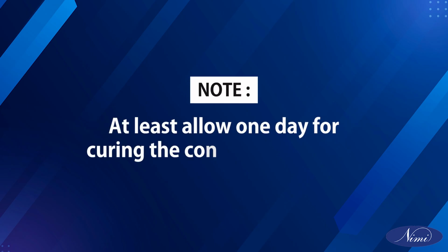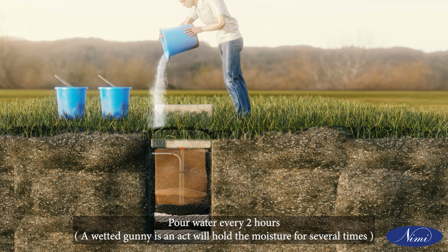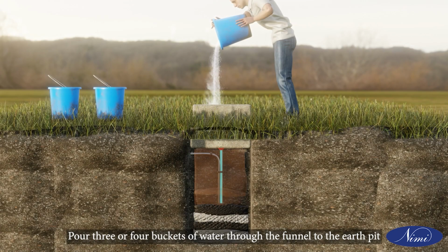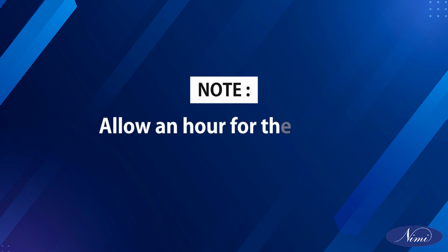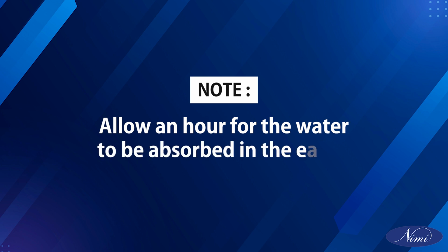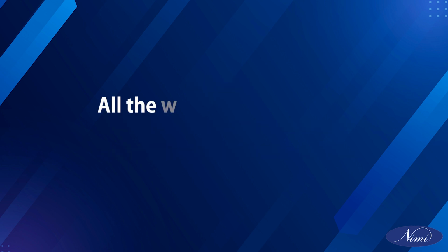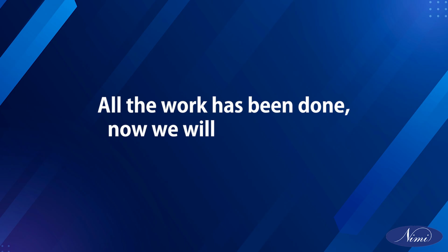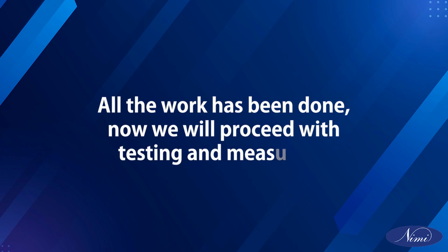Note: at least allow 1 day for curing the concrete structure. Pour water every 2 hours. A wetted gunny sack will hold the moisture for several hours. Pour 3 or 4 buckets of water through the funnel to the earth pit. Note: allow an hour for the water to be absorbed in the earth. All the work has been done. Now, we will proceed with testing and measuring.